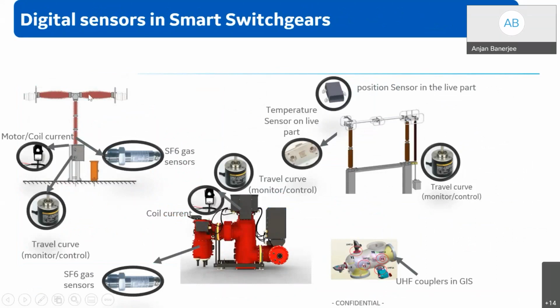Say, for example, in the circuit breaker, we need to offer digital sensors for SF6 gas temperature and pressure measurement. We also need sensors for motor coil current measurement, and a position sensor to monitor the contact travel of the circuit breaker. In the case of GIS, over and above all the sensors I mentioned just now, we also need to offer ultra high frequency antennas at various strategic locations of the GIS, as this antenna captures the ultra high frequency signal originating during partial discharge, which we will see in the subsequent slide.